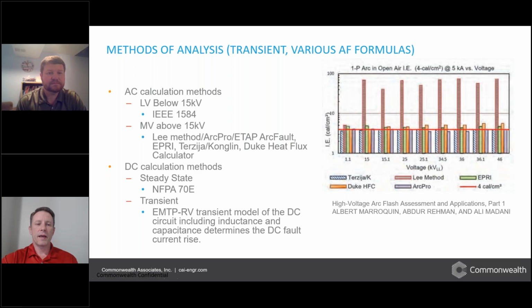For the AC calculation, for low voltage, we usually use IEEE 1584 to calculate it. There's several methods for medium voltage, which is considered anything above 15 kV. The Lee method used to be the standard, but it tends to give inflated values. Sometimes that's less of an issue because it's the low side that the arc flash is bad on, but we try to use the other methods to give a little more realistic values.